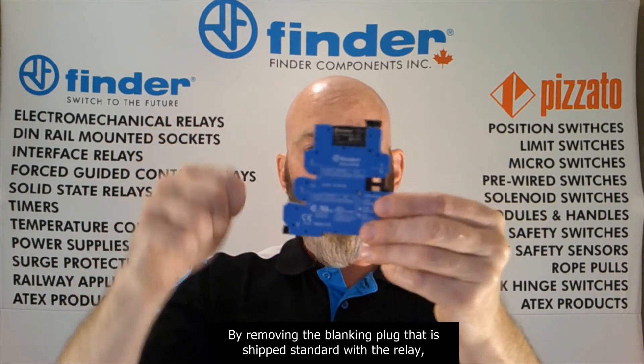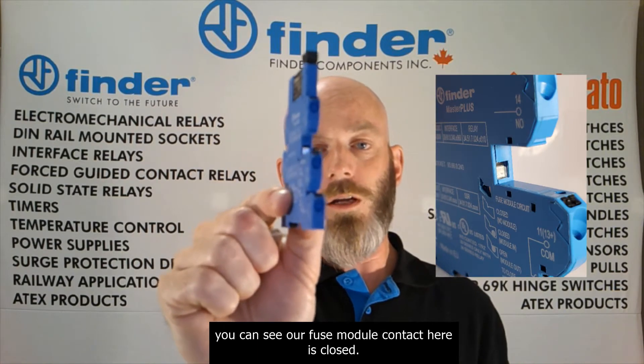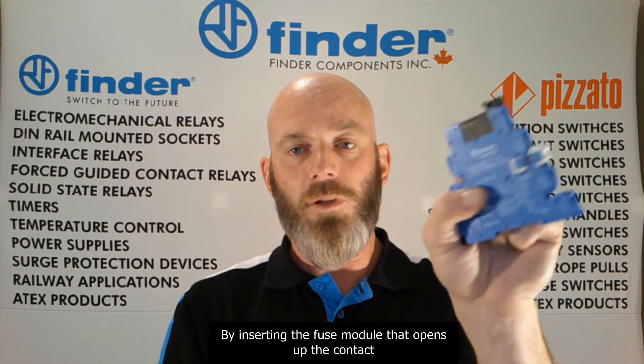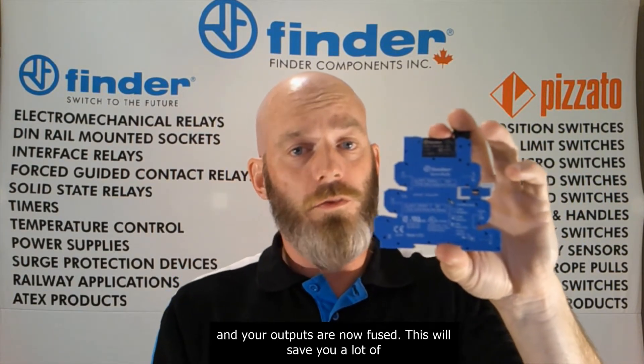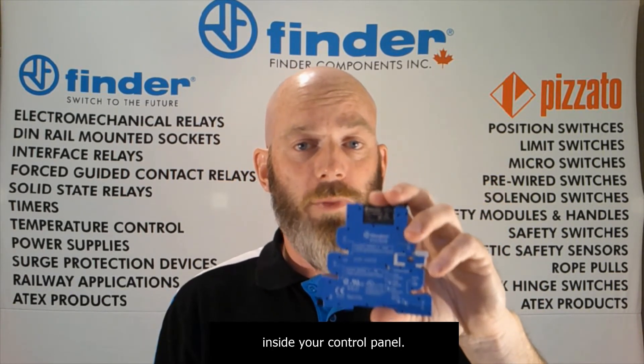By removing the blanking plug that is shipped standard with the relay, you can see our fuse module contact here is closed. By inserting the fuse module, it opens up the contact and your outputs are now fused. This will save you a lot of panel space and wiring time by not having to use any fuse terminal blocks inside your control panel.